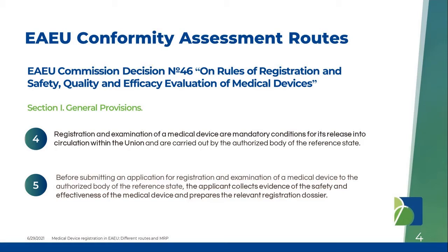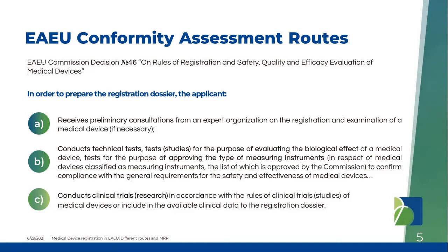Registration and examination, they mean expertise of a medical device, are mandatory conditions for its release into circulation within the Union. And before submitting an application for registration and examination of a medical device to the authorized body of the reference state, the applicant collects evidence of the safety and effectiveness of the medical device and prepares the relevant registration dossier. And from the point 6 of this decision, what applicant should do to prepare the dossier.